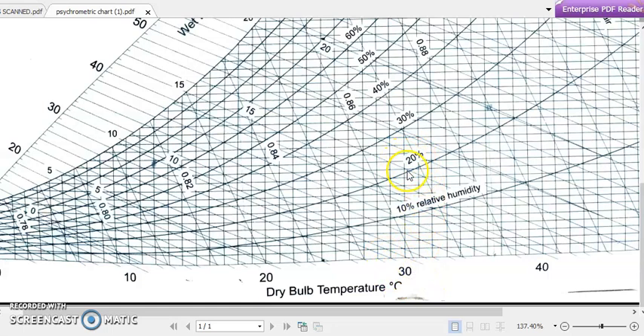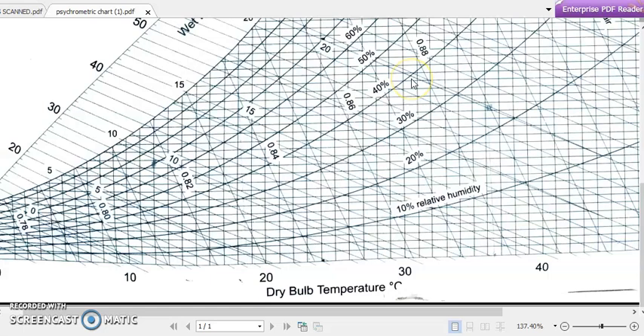At 6 degrees Celsius dew point, dew formation will begin for atmospheric air at 30 degrees Celsius dry bulb and 20 percent relative humidity. If the same air at 30 degrees Celsius has a higher humidity, say 40 percent relative humidity, drawing a horizontal line to the saturation line gives a higher dew point temperature. Even though the dry bulb temperature remains the same, dew point temperatures can easily be found using the psychrometric chart.